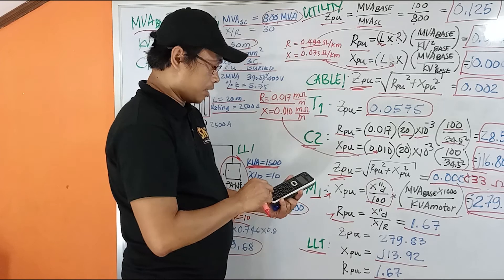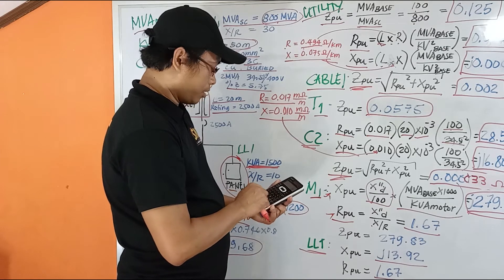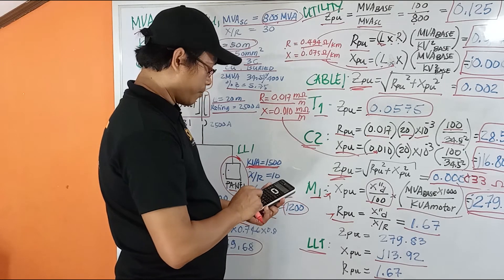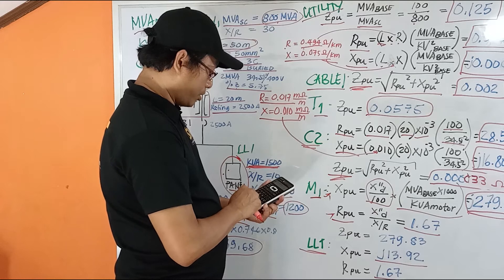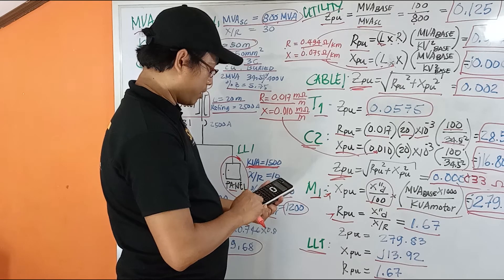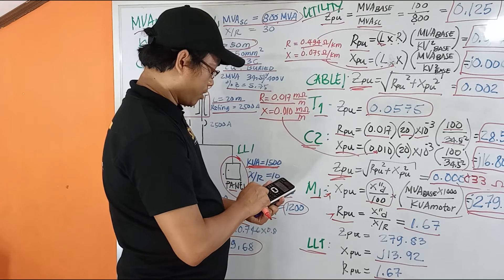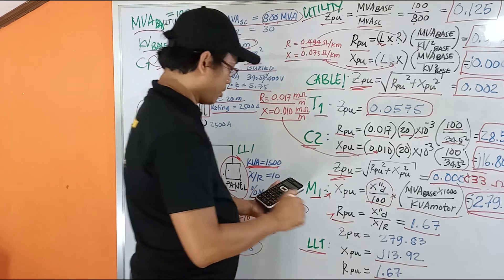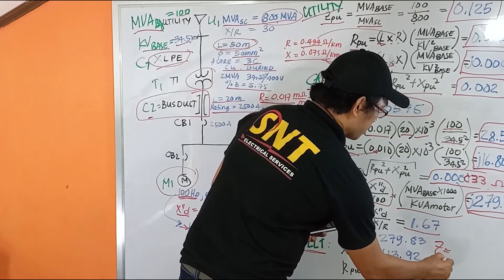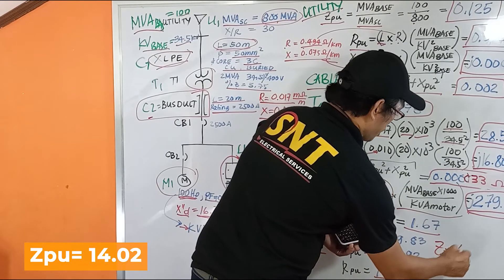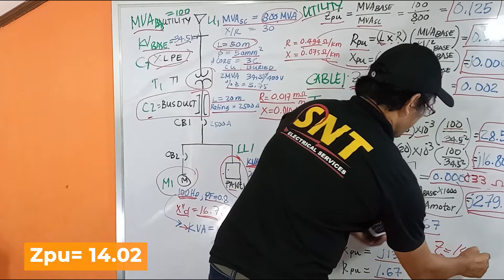The result of our XPU is 13.92 and our RPU is 1.67. Then we get the impedance: square root of 13.92 squared plus 1.67 squared. The impedance here is around per unit 14.02.